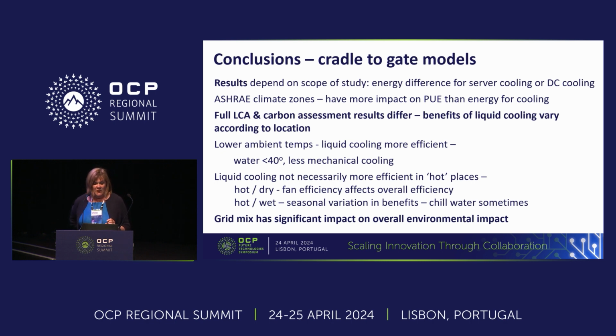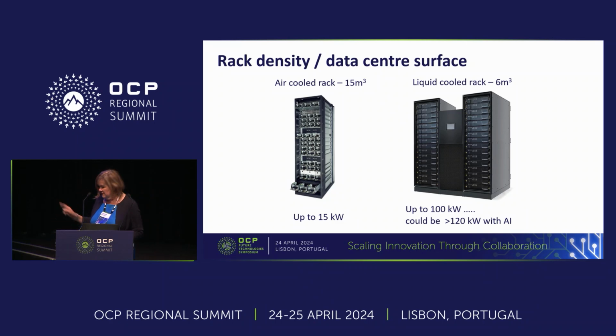The lower ambient temperature makes liquid cooling more efficient because a water temperature of less than 40 degrees means that you need less energy for mechanical cooling. So it's a sort of agglomeration of different factors here. Liquid cooling is not necessarily more efficient in very hot places because of fans, etc., which affect overall efficiency. And a key thing is that you have seasonal variation, specifically in hot, wet areas, and sometimes you do have to chill water because it's above 40 degrees. But the very important influencer on all of this is the grid mix, which has a major impact on overall environmental impact. And I'm going to hand over to Stefan.